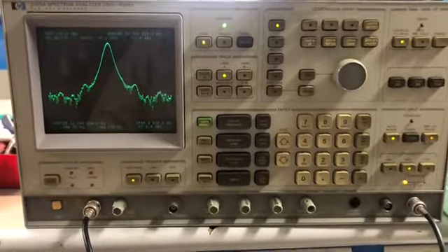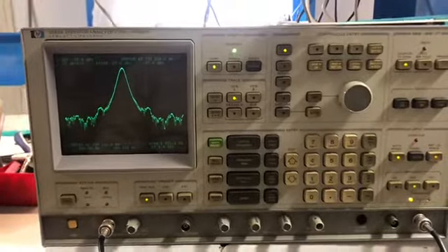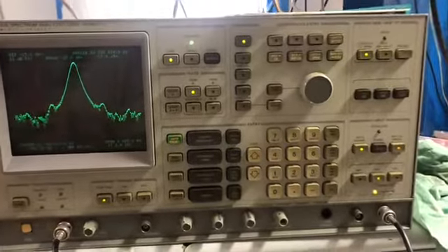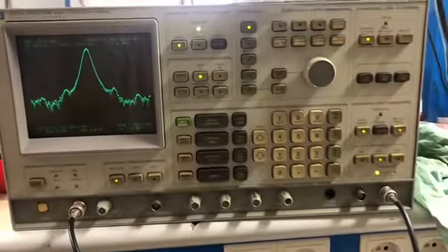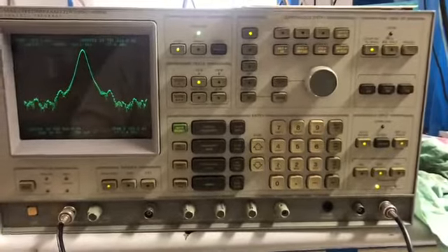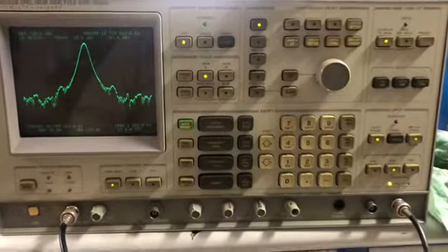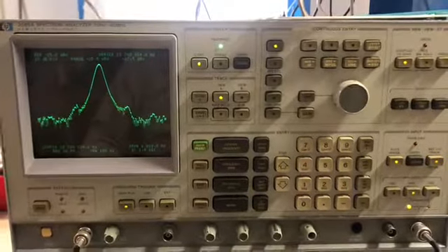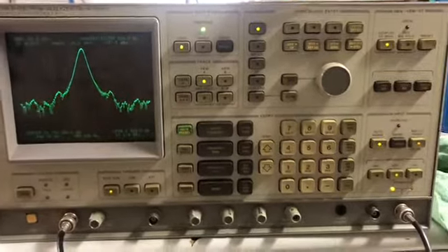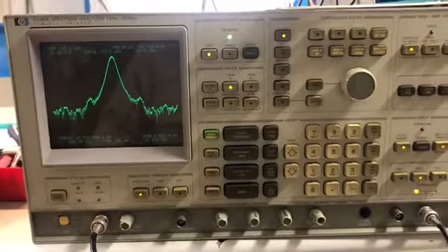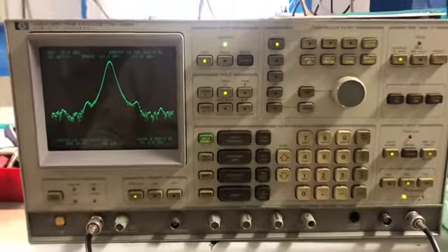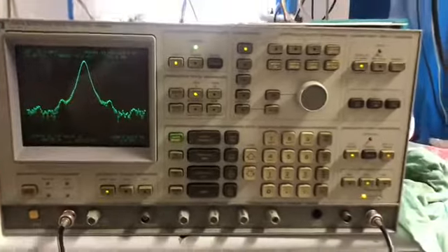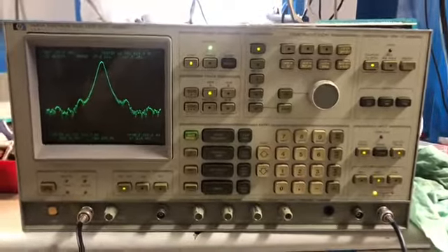So in total, I have replaced in this instrument something like 25 ICs all around, the clock generator and in the CPU board as well, some buffers. Of course, not all of these replacements have been included in this video because I've been in this instrument many times in the past years trying to fix it. But then I decided to buy the signature analyzer, and that made the difference.